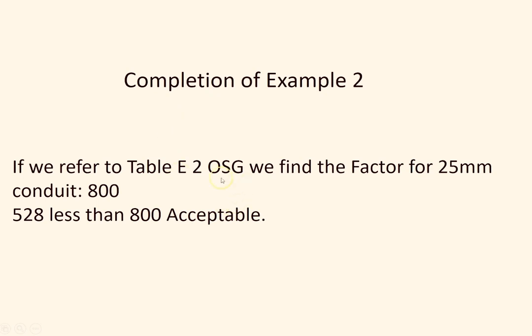And the completion of example 2, if you go to table E2 of the on-site guide, you can find a factor for 25mm conduit of 800. So I now know that I can use a 25mm conduit.